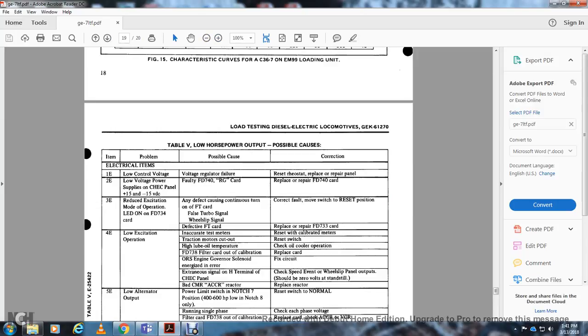Alright, your electrical items. 1E, low control voltage, possible cause, voltage regulator failure, correction, reset rheostat, replace or repair panel. Item 2E, low voltage power supply with the constant horsepower acceleration control current panel with a 15 plus or negative 15 volt DC, faulty FT740RG card. Replace or repair the FD740 card. 3E, reduced excitation mode of operation, LED on the FD734 card.